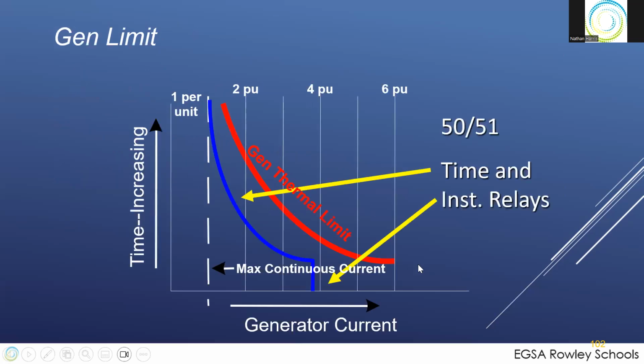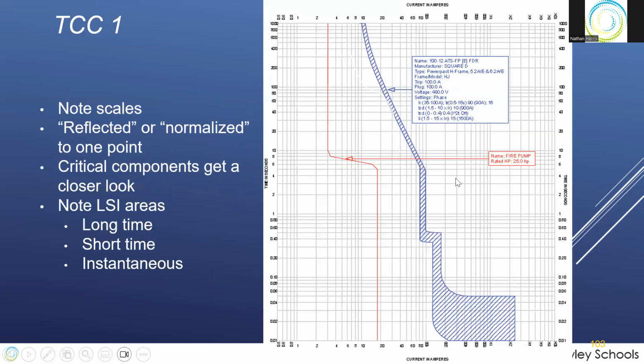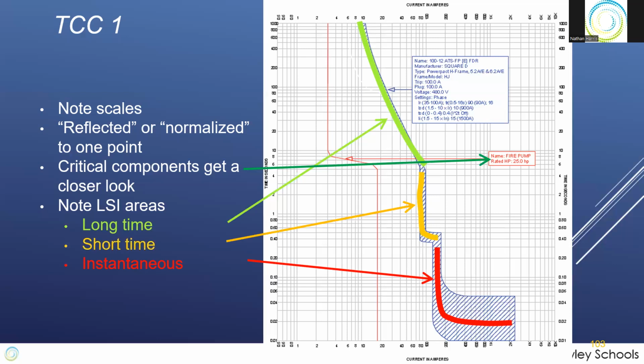When you're doing a coordination study or you want to protect against the generator thermal limit from being burned up over time, this is the breaker settings to protect that unit. Here's a real-time current curve showing this. In this case, this is for a VA hospital. And so here's the breaker curve. And in this case, we have a fire pump. We want to make sure it's protected against having a problem or a cross of the curve. And so here's the long time part of the curve, the short time, and the instantaneous part of the curve of an LSI unit.